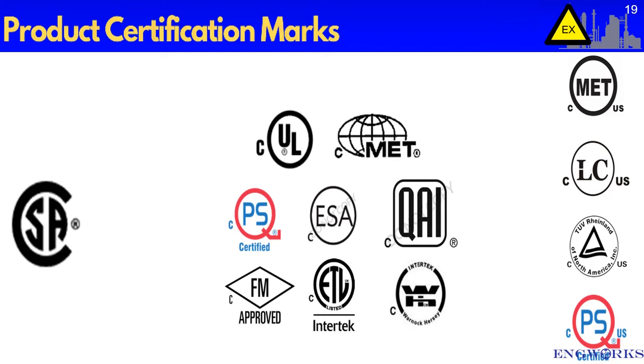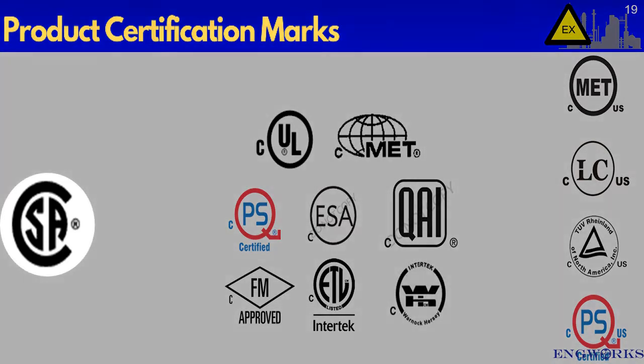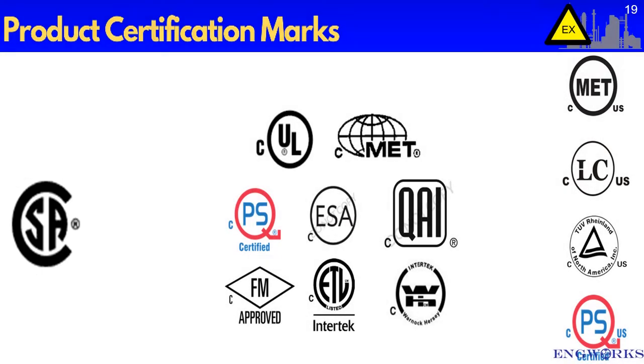A certification mark is evidence of a product's approval. Let's look at a few examples. The CSA mark by itself implies Canadian approval. Other certification bodies will indicate a Canadian approval by placing a small c adjacent to their certification mark.